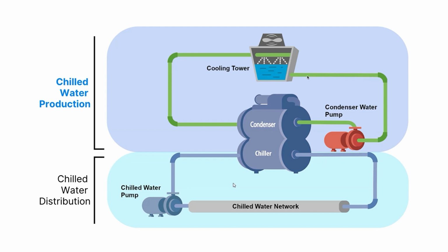And you're leaving a huge amount of opportunity for efficiency on the table by running that set point there year round. Because in some conditions where your wet bulb temperature is significantly lower, you could actually lower that temperature set point. So rather than a constant condenser water temperature set point, a common rule of thumb is wet bulb plus 4 degrees, for example.